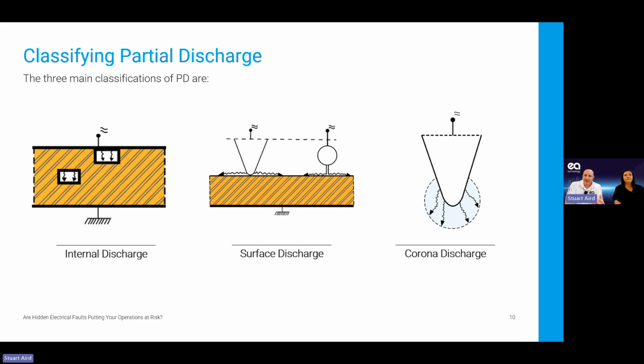So you will get electromagnetic waves, but they're quite weak for the surface discharge. The amount of energy in each discharge is quite low. So although electromagnetic waves will be there, they might not be as easy to detect in normal operating conditions. For the surface discharge, we try to focus on the sound, because although there is the light that we talked about, unless you can see inside the area where it's happening while it's in normal operating condition, it's quite difficult. So we generally focus on the sound. We can hear that crackling type sound through a vent or through a contact probe.